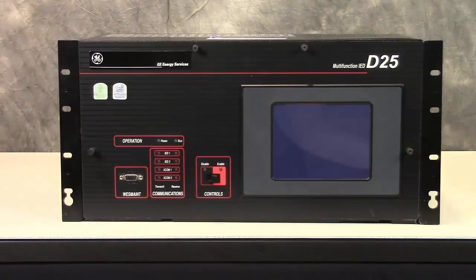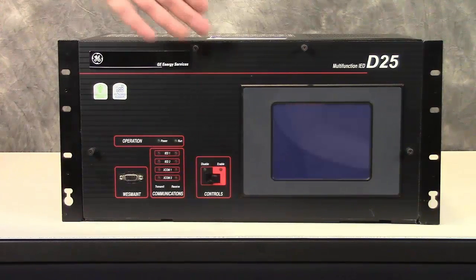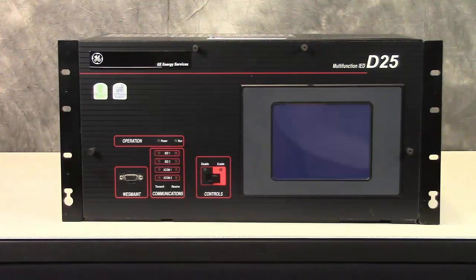It gives you more than the simple maintenance port because it's a fully functional touch screen available on the bay controller. It's secure because you'd use passwords if you want to do controls from inside the single line diagram, which is fully animated and can be set up either by GE or by your local representative.